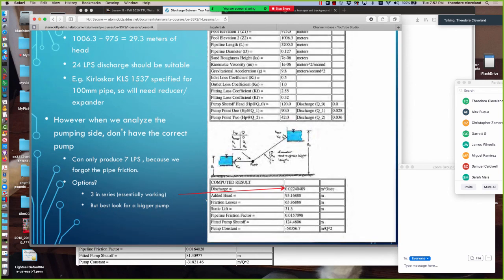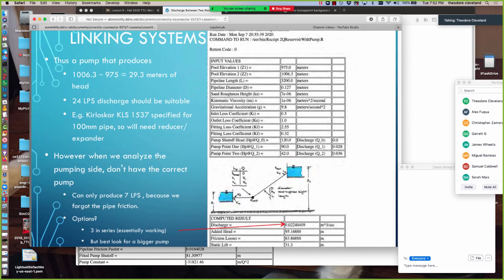So the one comment I have is the single pump produces 7 liters per second, which is about all we need if the schoolyard valve is left open for any duration. And so that will work fine. And the other 2 faults, the float valve failing, a pipeline break, that's going to be a major interruption of service. And that would probably be, well, that was what was designed. So the actual design can handle the valve at the delivery end being left open unintentionally, but the other 2 faults, you have to shut the system down and repair it, which is typical.